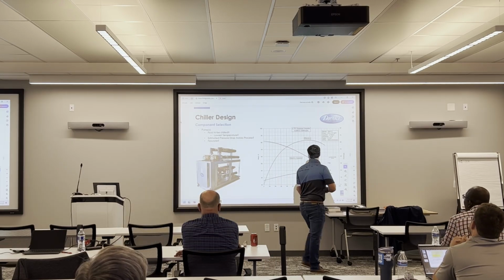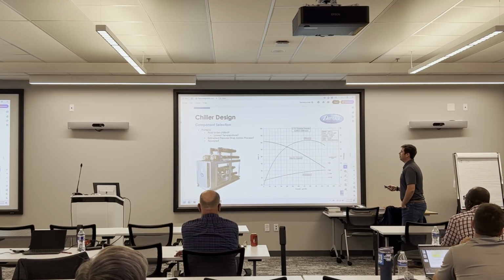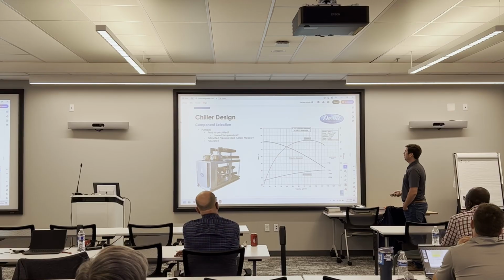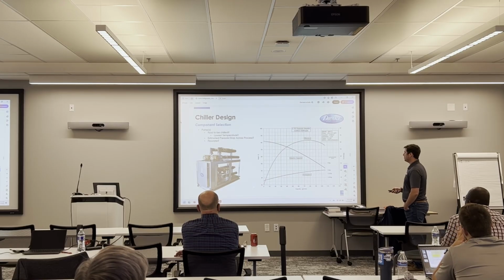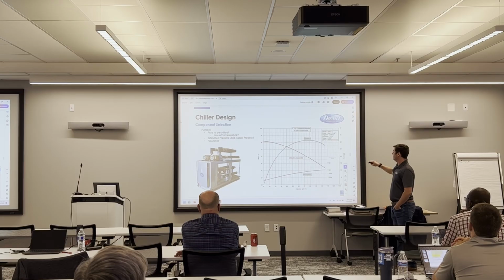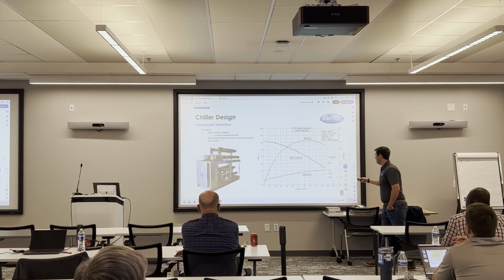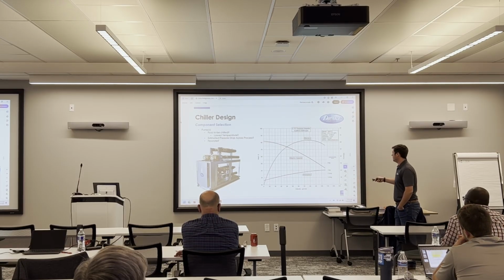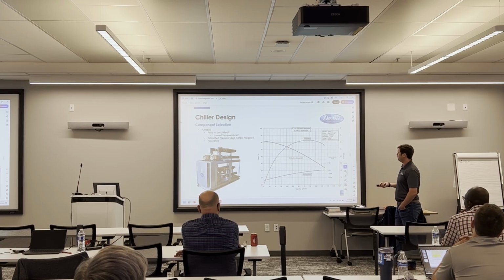On the left-hand side, this represents the pressure drop across the pump. This is expressed in feet of head. You can convert that to PSI if that's easier for you. On the bottom here, we have the capacity of the pump in gallons per minute. These lines represent the horsepower limitations of the pump. So this is a 2 horsepower motor, and this is our 2 horsepower line right here. Essentially what I'm trying to say is, don't pick a pump that's going to operate more than its rated horsepower.